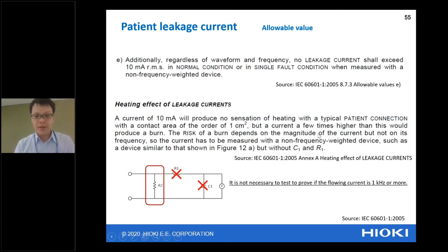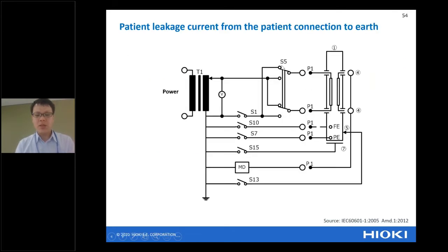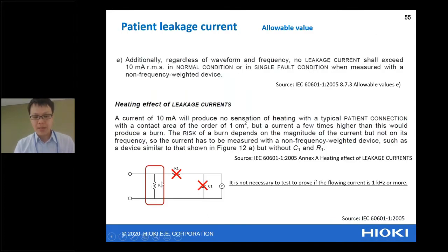Okay, regarding patient leakage current, the standard mentions that you should measure both the AC situation and the DC situation. As I told you, the human body is like this, resistance and capacitance. So it means you can measure only the AC component of the leakage current. But if you want to measure the DC component of the leakage current, in that case, ST5540 can turn the filter off. If the filter off function is on, you can see the DC component of the leakage current. So in that case, also, ST5540 is very, very convenient for doing the measurement from the standard.